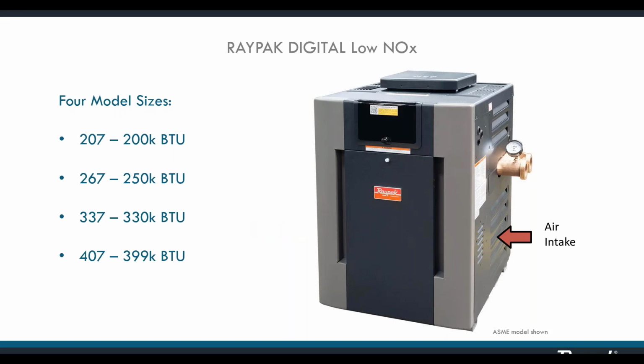The low NOx sizes mirror the sizes available in the atmospheric model. The BTU input is the same. You will notice that the model sizes end in a 7 instead of a 6. One way you'll know a low NOx from the atmospheric models is this air intake on the right side of the cabinet. This is where the fan pulls in combustion air. Make sure this intake always remains unobstructed.